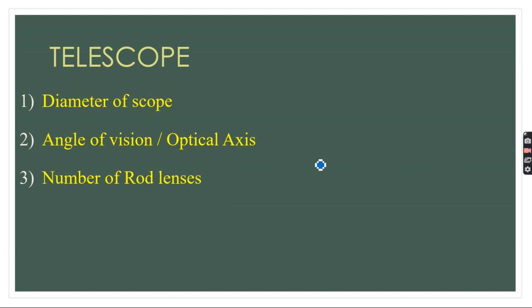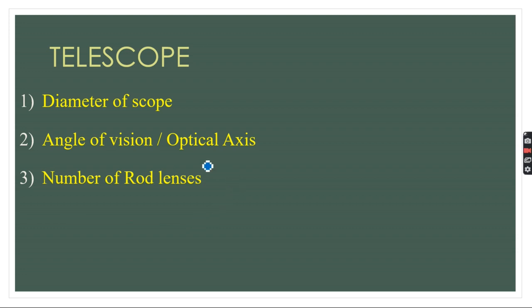In any telescope there are three important properties. First is the diameter of the scope — how much is the circumference of the telescope shaft. Second is the angle of vision, also known as the optical axis — the angle between the optical axis and the longitudinal axis of the scope. Third is the number of rod lenses: the more the number, the better the vision.